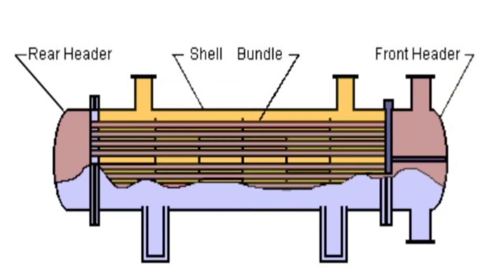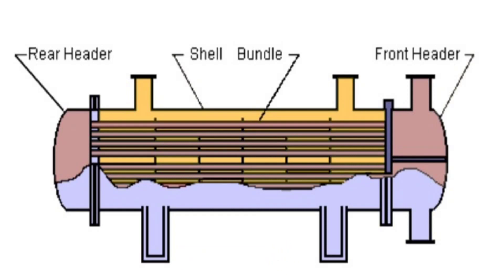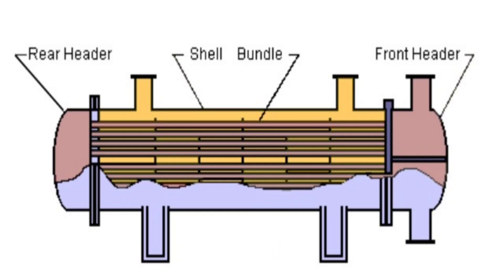A shell and tube heat exchanger consists of a number of tubes mounted inside a cylindrical shell. Two fluids can exchange heat: one fluid flows over the outside of the tubes while the second fluid flows through the tubes. The fluids can be single or two phase and can flow in a parallel, cross-counterflow, or counterflow arrangement. The shell and tube exchanger consists of four major parts: the front end, where the fluid enters the tube side of the exchanger, and the rear end, where the tube-side fluid leaves the exchanger.